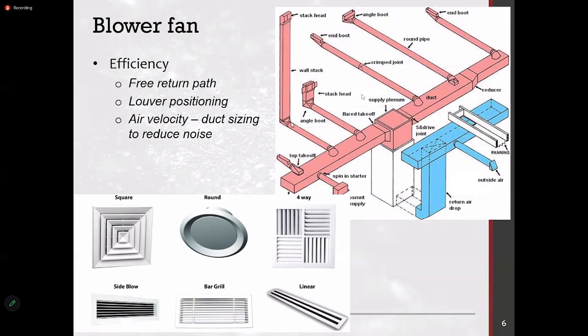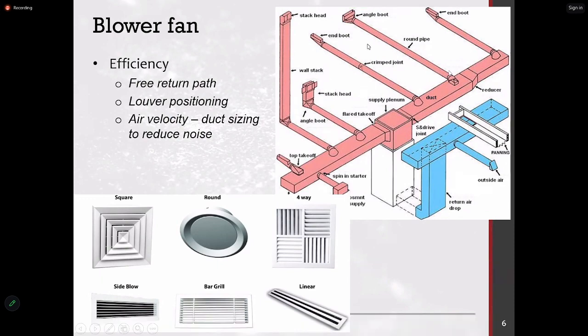So it is a somewhat continuous process, because if you start from the first one and you decide how much air should be coming out of the louver, you measure that, then you reduce that, then you go to the next one and you adjust that. Once you go to the last one, you have to come back and do it a second or third time. So it is a continuous improvement kind of process, because once you adjust the first one, the next one will be higher. It is like a balloon where you make equal holes to get an equal air distribution. So continuously, at least about 3 times, you have to adjust the dampers to the value you require. Because sometimes if your adjustment is too high, then the air volume will reduce, and the longest one will have more air. So that is also not recommended. So that is with regard to duct sizing and air velocity.